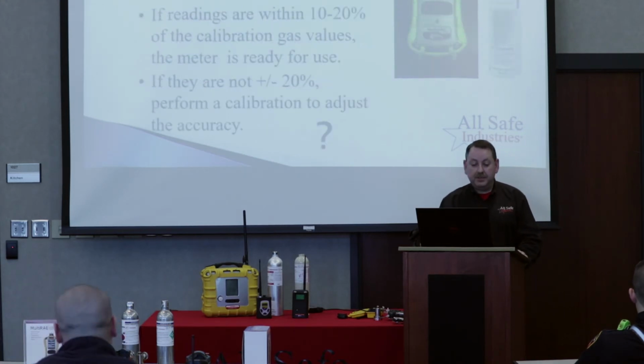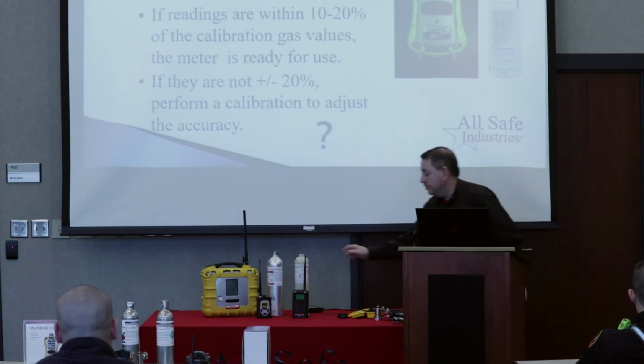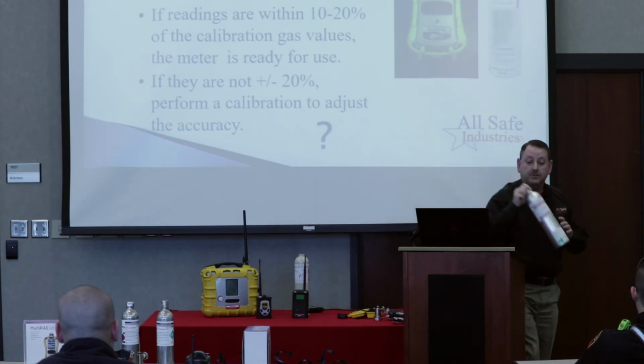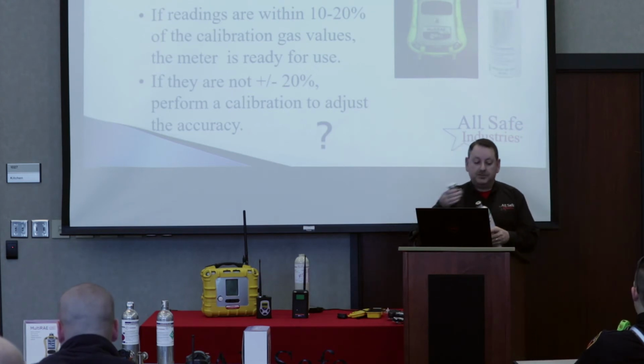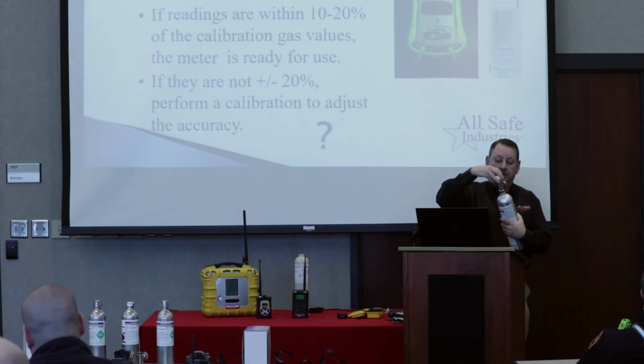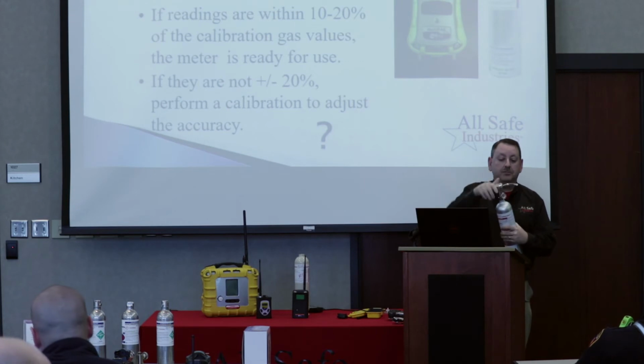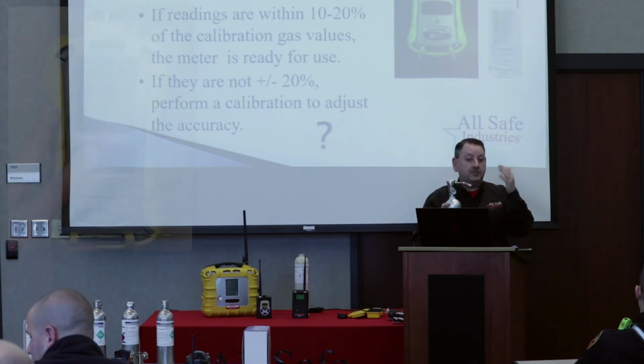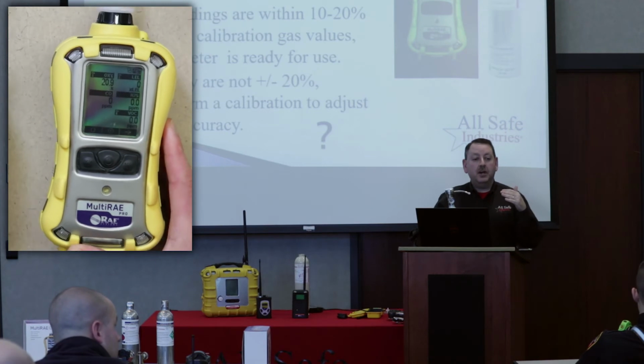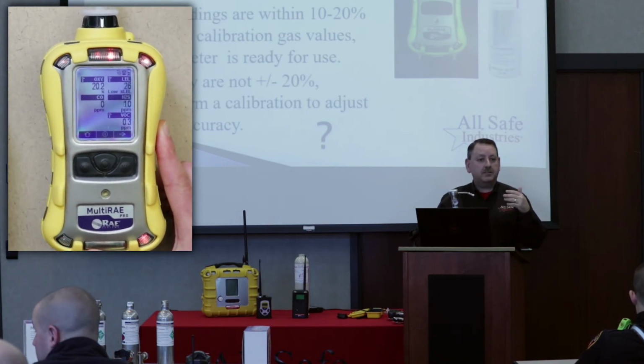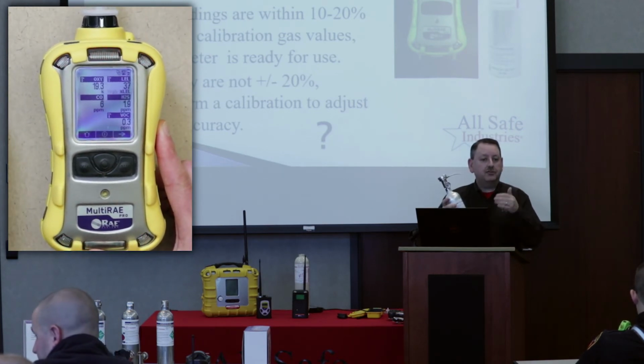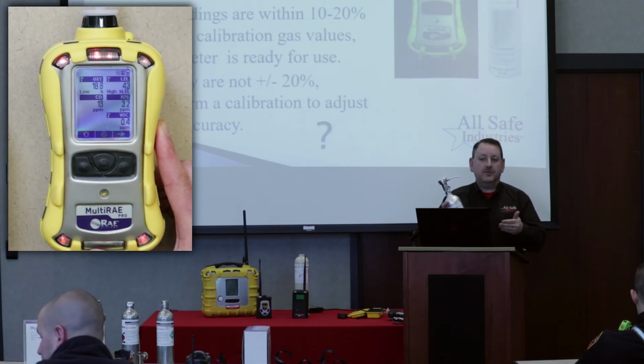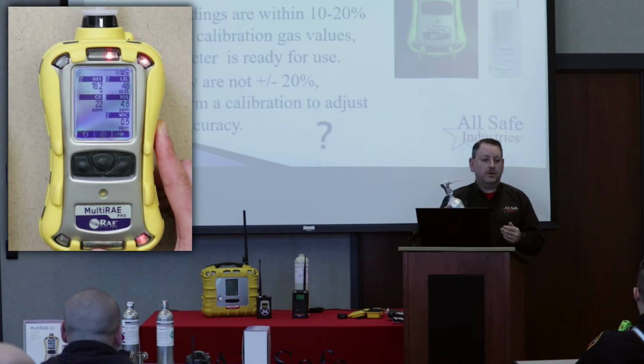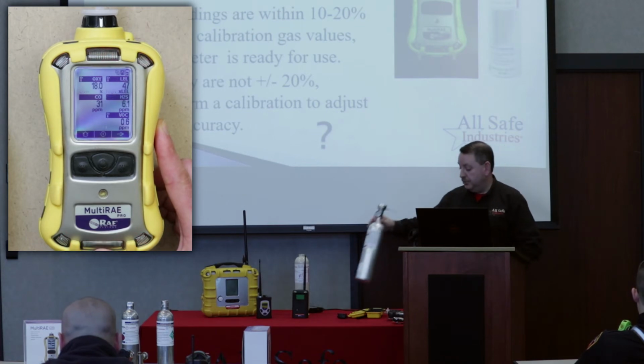So the next step is your bump check. And this is where you'll literally take your cylinder of gas. Again, this is if we're doing this manually. You take your cylinder of gas with your regulator engaged, and you'd simply attach your meter to the gas and just watch what happens. The meter doesn't know if you're in a confined space or if you're drawing from a cylinder because you're in regular run mode. It's just going to start reacting to the gas, and that's how we confirm for ourselves that the sensors are actually working properly, okay?